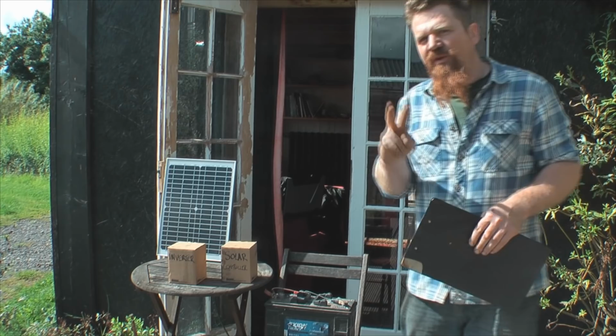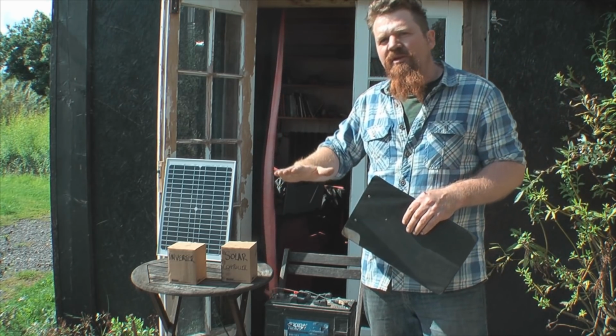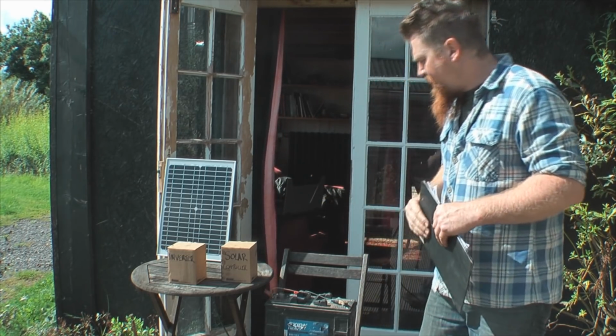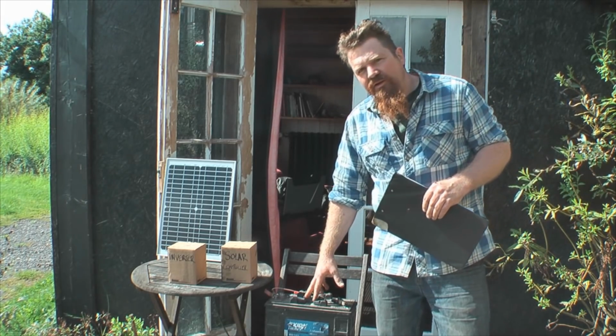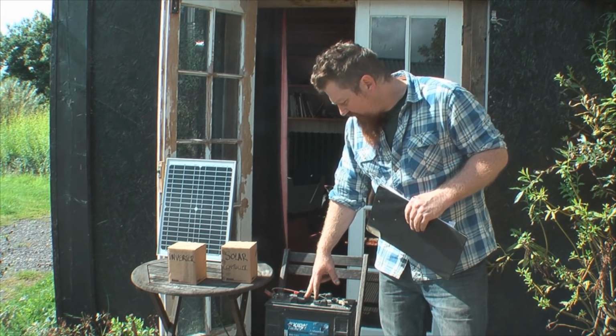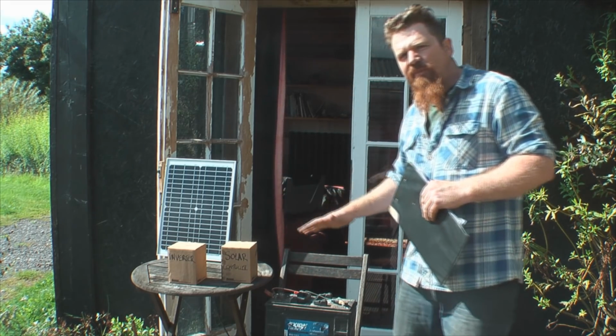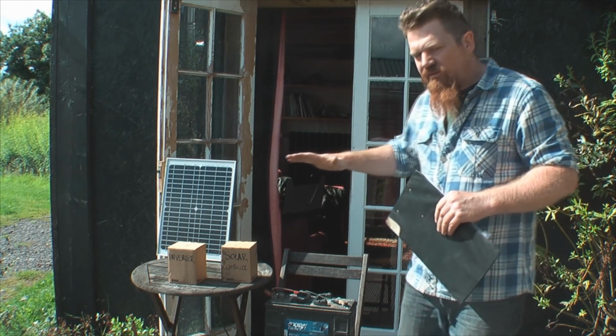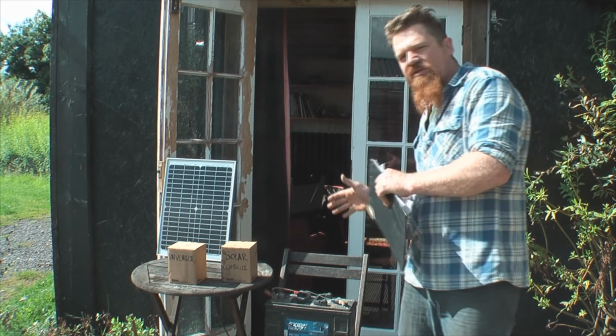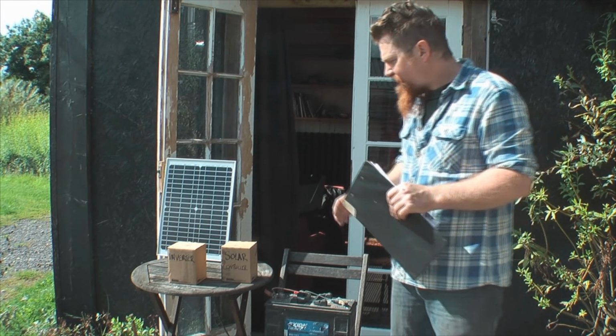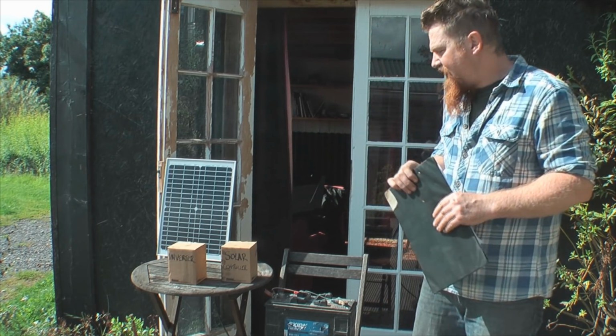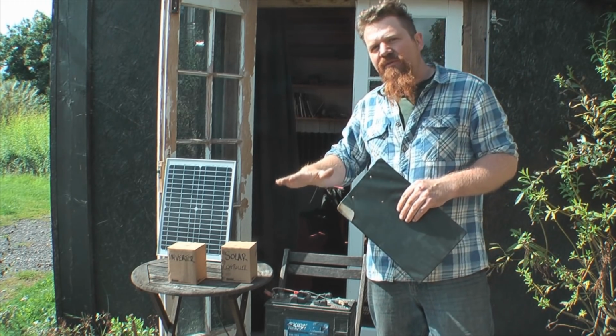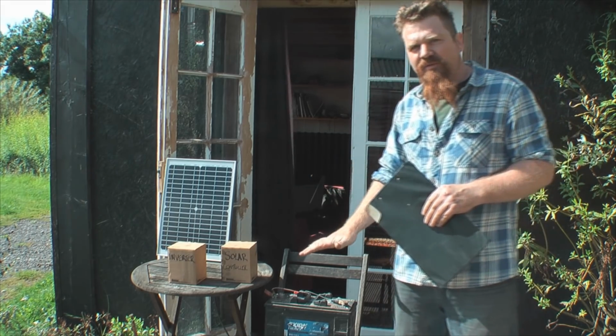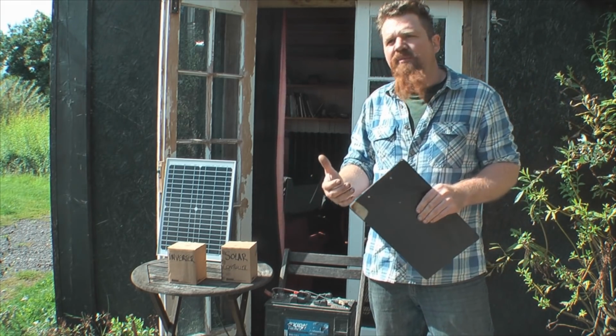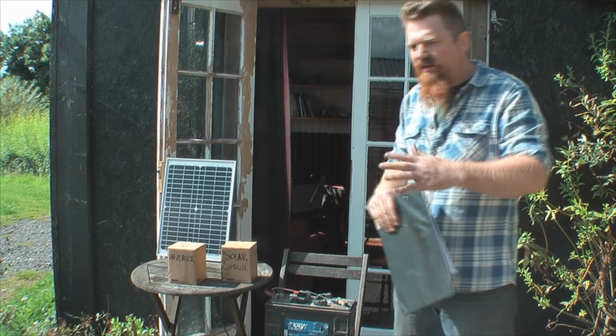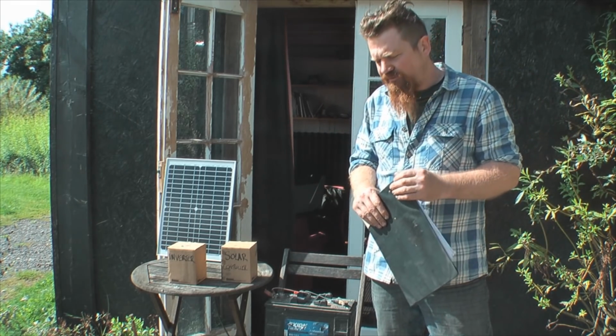The other really important thing about batteries is to never discharge them more than 50%. If this battery here is 110 amp hours or so, that means I could only treat it as if it was a 50 amp hour battery, and you have to factor that into your calculations. It's very important to never go below 50% on a deep cycle battery, because again it will sulfate up, be damaged, lose effective capacity, and be scrapped within a year or two.